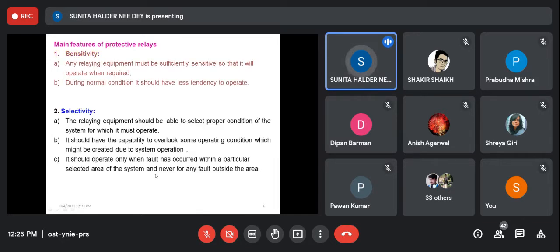Next is selectivity. So if we set a relay to protect a particular device, a particular generator in a power system, say there are 10 generators, and we have set a relay to protect generator 2 only, then it should protect generator 2 only, not the others. Otherwise, there will be unnecessary tripping, and when there is more tripping, more disconnection in the power system, then what will happen? Other sources will be overstressed because the load remains the same. We are not disconnecting load; we are disconnecting equipment. So if the equipments are getting disconnected, then the equipments which are still in the system will get stressed. So there should be proper selectivity. Whatever task is given to a particular relay, it should do that particular task, not more than that.